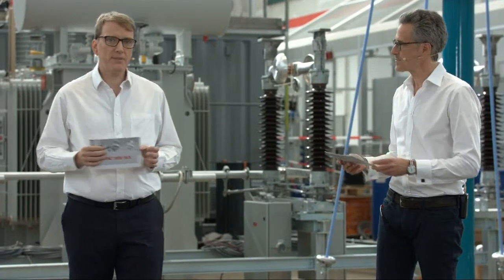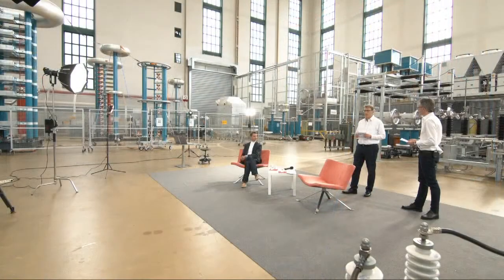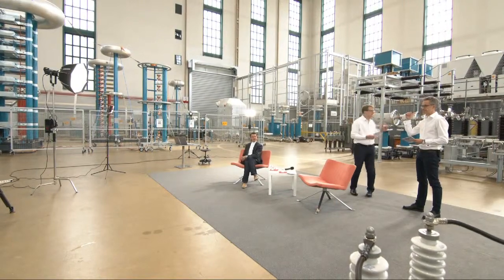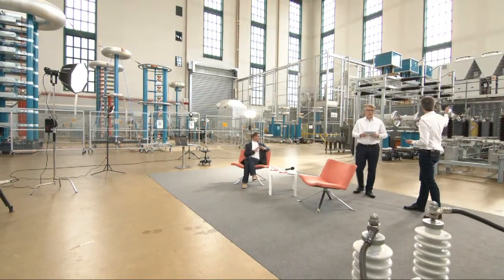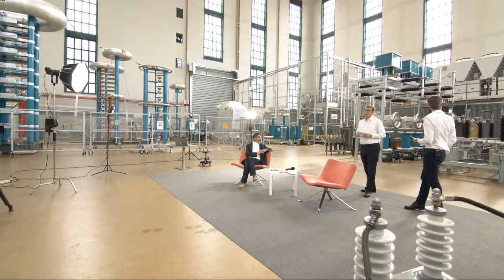Today we have something special in the background. What we can see there, this is altogether a transformer test field for induced voltage testing up to 3000 MVA, which is a huge amount of power. And there is also a highly precise loss power metering system, our LIMOS - the most precise industrial available power metering system you can get.